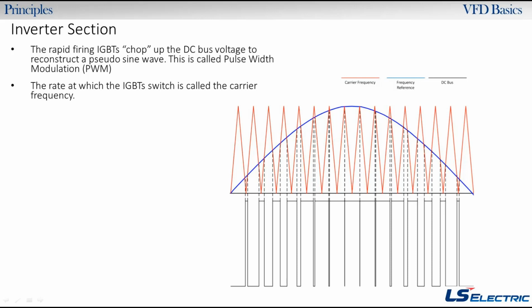Whenever this red one drops below the blue one, that's when we turn on those transistors. So we turn it on, then it goes above, we turn it off. We turn it on, we turn it off. Then you can see towards the peak, when this frequency reference is at the highest part, we're pretty much always on. We're leaving those transistors on for a very long time, and then we start turning them off more, and more, until they're almost all the way off. This is showing the firing of an IGBT on the positive side.